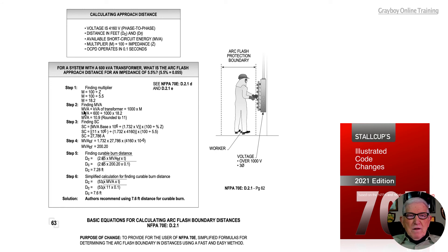Step two, to determine the MVA we take the kVA of the transformer which is 600, divide that by 1000, times the multiplier of 18.2. We come up with an MVA rating of 10.9 rounded up to 11.